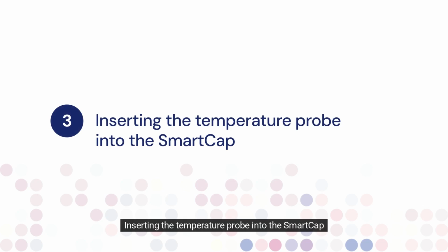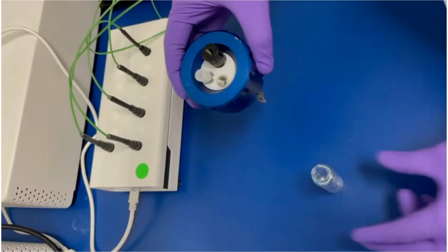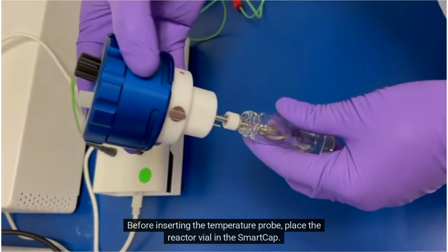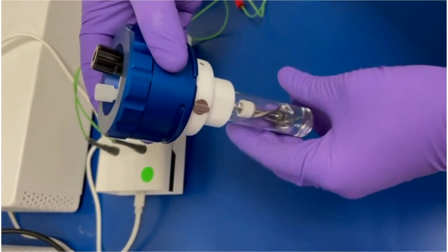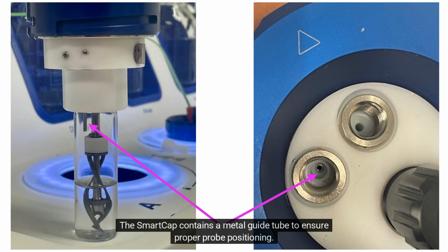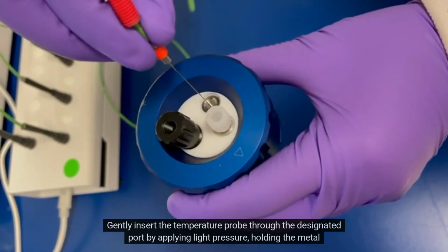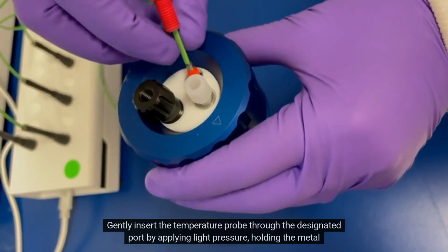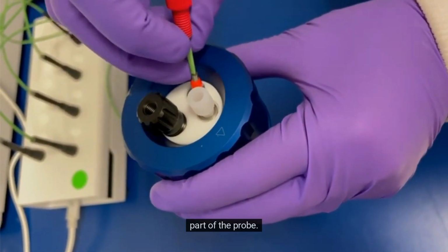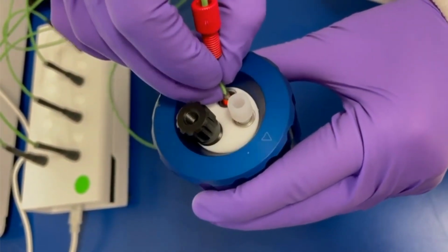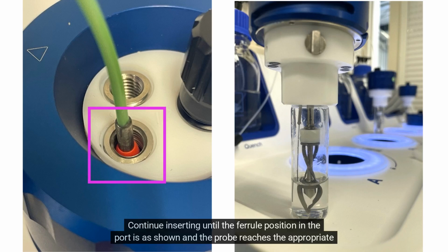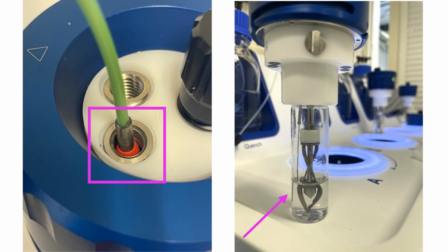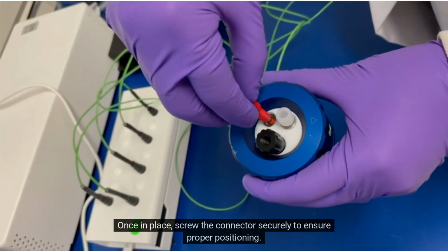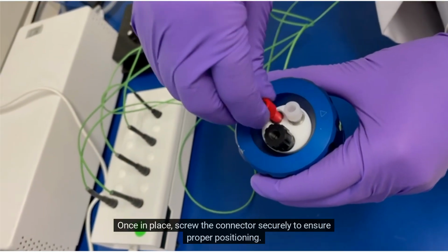Inserting the temperature probe into the SmartCap. Before inserting the temperature probe, place the reactor vial in the SmartCap. The SmartCap contains a metal guide tube to ensure proper probe positioning. Gently insert the temperature probe through the designated port by applying light pressure, holding the metal part of the probe. Continue inserting until the ferrule position in the port is as shown and the probe reaches the appropriate depth. Once in place, screw the connector securely to ensure proper positioning.